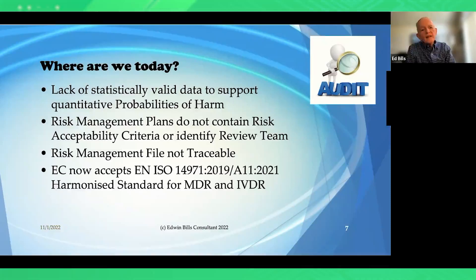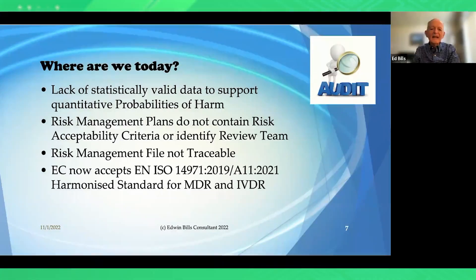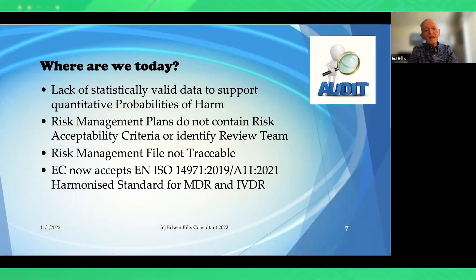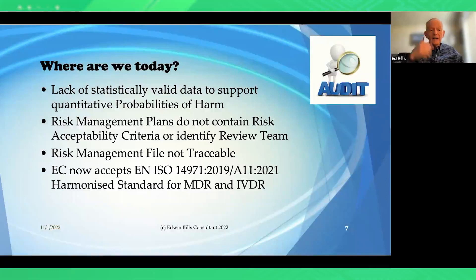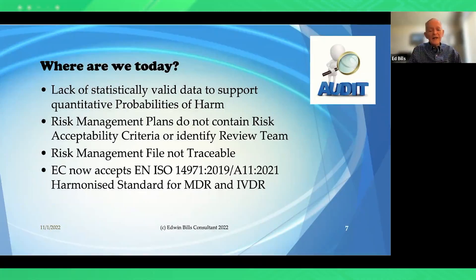Another common problem is a lack of statistically valid data to support quantitative probabilities of harm. You can't do quantitative probabilities without statistically valid data, which is why qualitative probabilities are allowable in the standard — addressed in approximately clause five. Risk management plans often do not contain the risk acceptability criteria or identify the risk review team, which is required under clause nine's risk management review. Another problem is that the risk management file is not traceable: clause 4.5 requires traceability and has specific elements — this is different from design traceability.